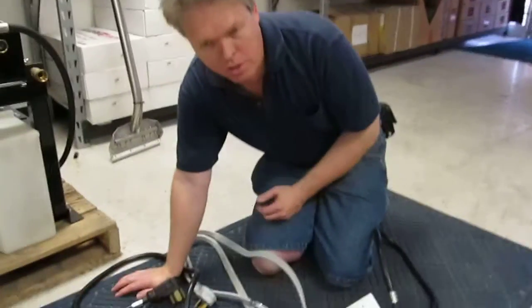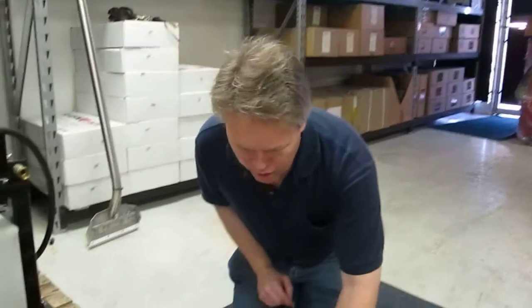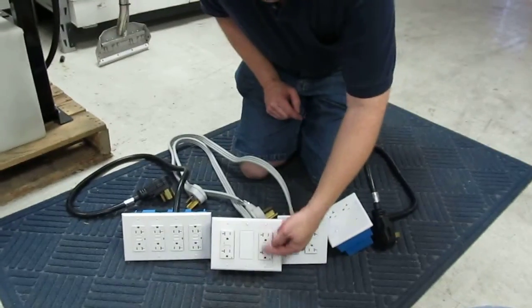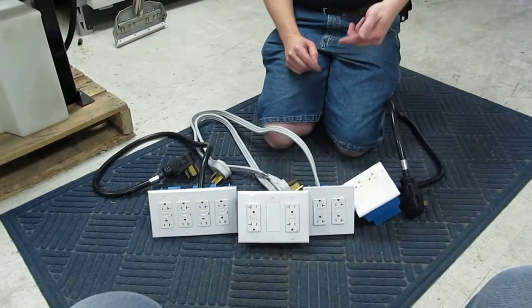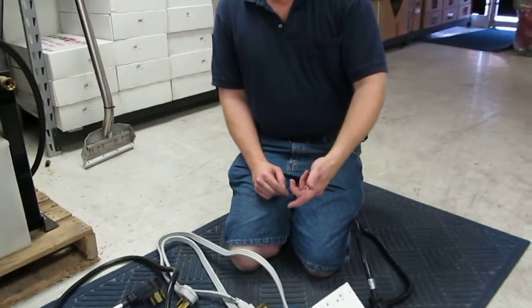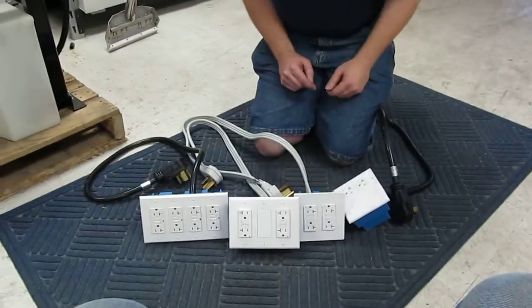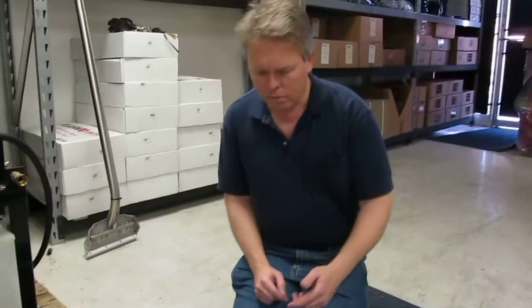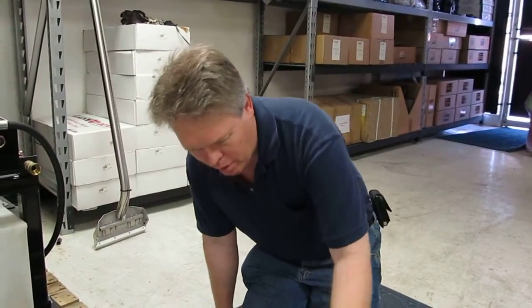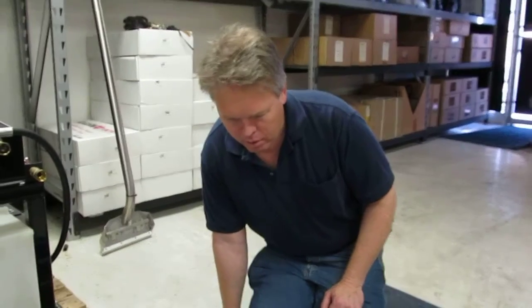The electrical codes state that when you're going to run something long term, you're not actually even supposed to go beyond 80% of what it's rated for. So if you have an outlet that's rated for 20 amps, if you're going to have something plugged into it for hours at a time, you're actually not supposed to plug anything in it past 16 amps. That's like if you're going to run a lot of dehumidification equipment on it.